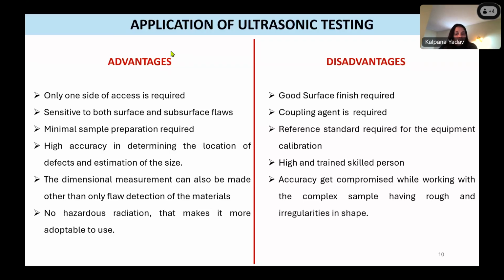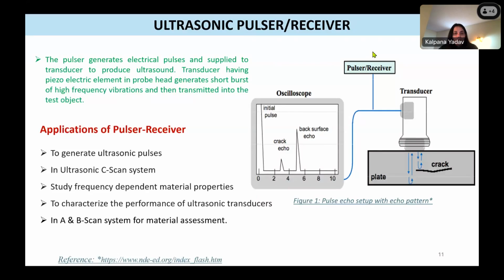It also takes a lot of exhausting work, and accuracy is compromised when working with complex samples, because roughness and irregularities in the shape cause a lot of energy loss in the sample. You get a lot of noise, and if your signal is coming from some irregularity or defect, you cannot tell whether it is a noise signal or an actual signal from the defect. So accuracy is compromised when working with complex samples.